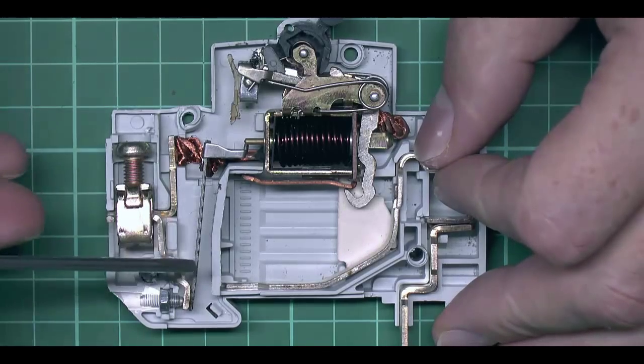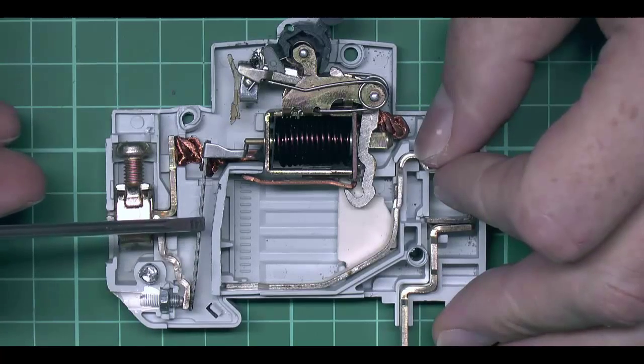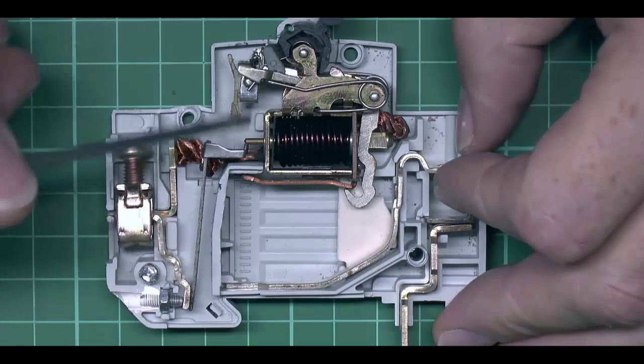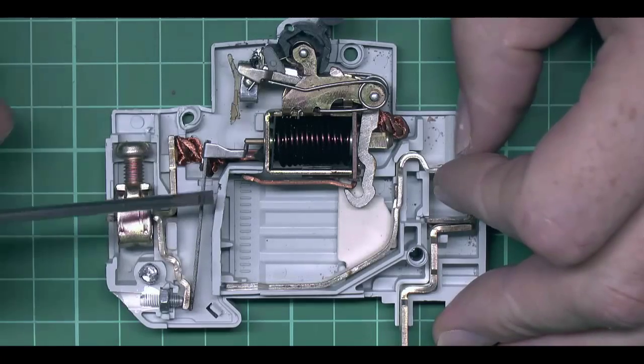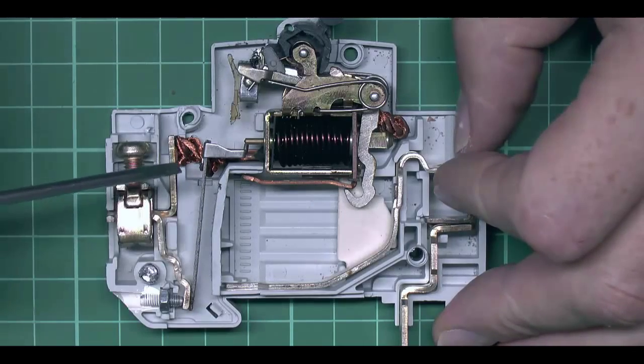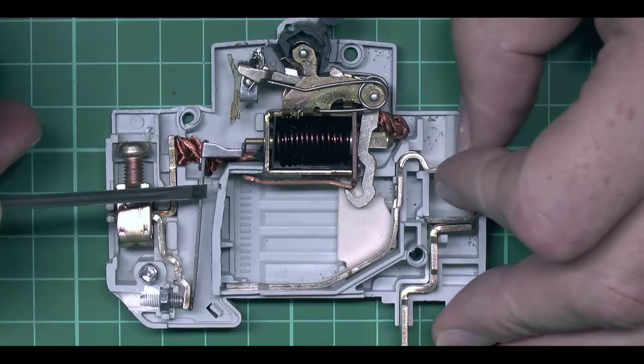And this is the part which would typically react to smaller types of overload. So say for example on the 6 amp circuit breaker we have here, if say 10 amps was passed through it, and of course that would slowly heat up and cause the device to trip.